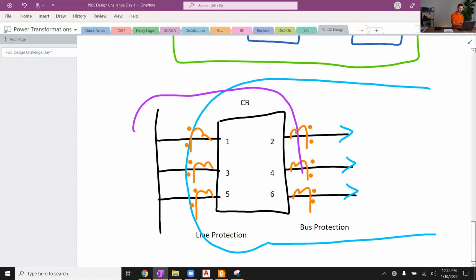That's going to be like this. Notice how the line and the bus protections overlap. We call that overlapping zones of protection. But essentially the polarity dots coming on this side are into the line zone of protection, the way we drew this. Here the polarity dots are into the bus zone of protection. So that's the reason that breaker manufacturers will standardize on sending you the breaker bushing CTs with that reverse polarity dot notation like that.